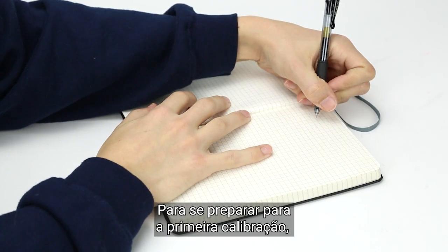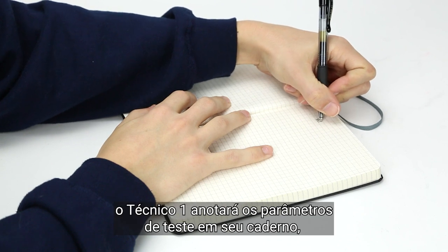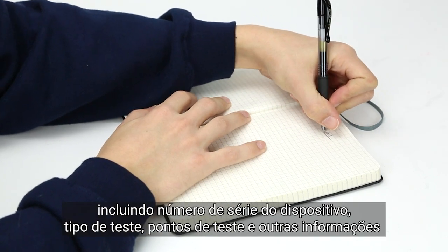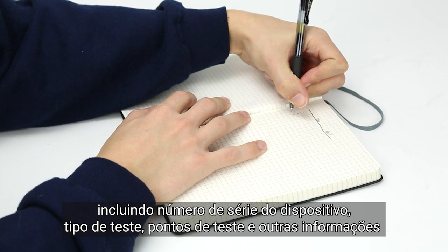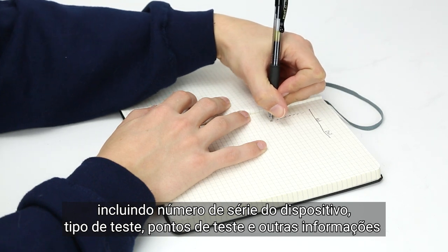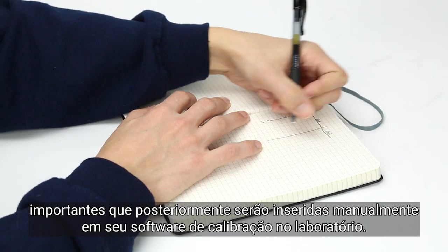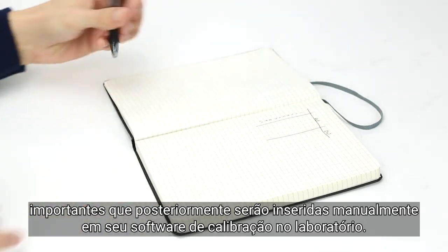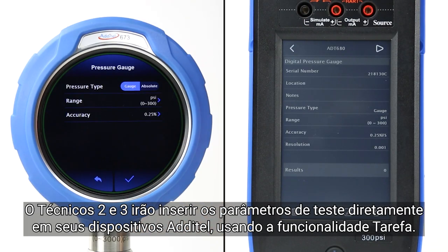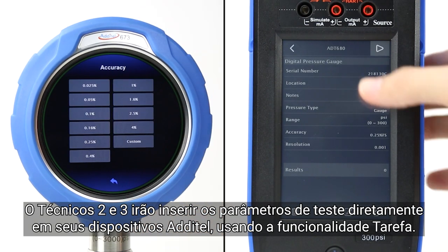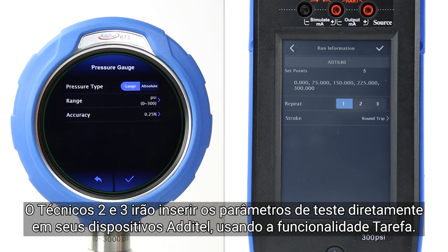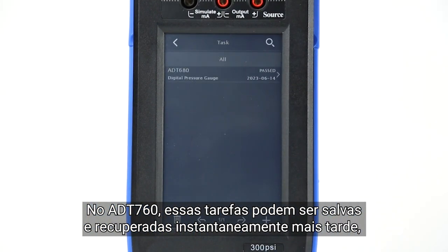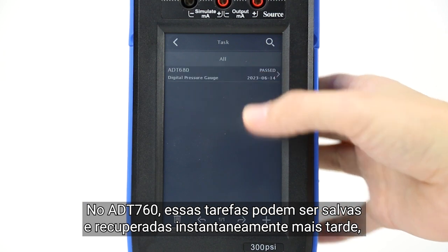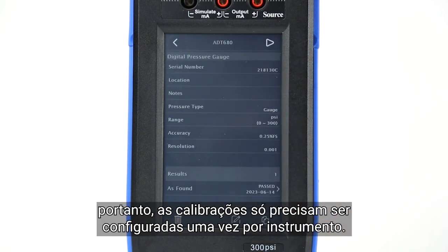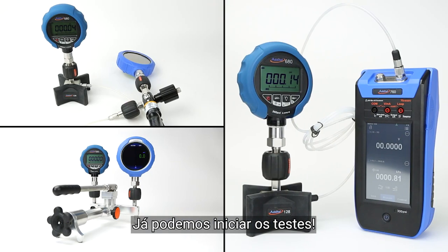To prepare for the first calibration, Technician 1 will write down the testing parameters in their notebook, including device serial number, test type, set points, and other important information that will later be manually entered into their laboratory calibration software. Technicians 2 and 3 will enter all of the testing parameters directly into their Additel devices using the task feature. On the 760, these tasks can be saved and recalled instantly later, so the calibrations only have to be set up once per device. Testing can now begin.